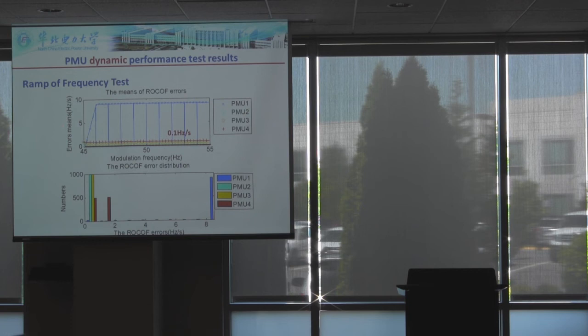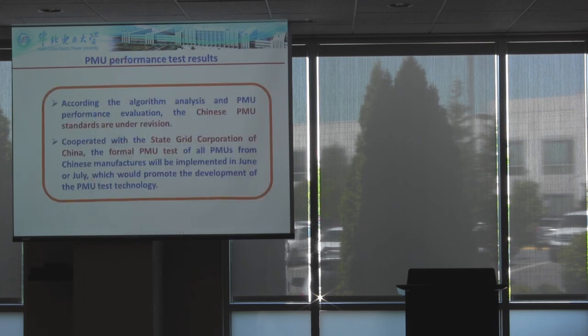Here is the ramp of frequency test. And actually in the Chinese standard, there is no requirement about the behavior under the ramp of frequency condition. So that's why the behaviors are not so good. According to the algorithm analysis and the PMU performance test results, right now the Chinese PMU standards are under revision, and in cooperation with the State Grid company, the formal PMU test of all PMUs from Chinese manufacturers, maybe also from overseas, will be implemented from June 15th until July 15th, by which we hope we can provide a solid basis for PMU applications and promote PMU technology.